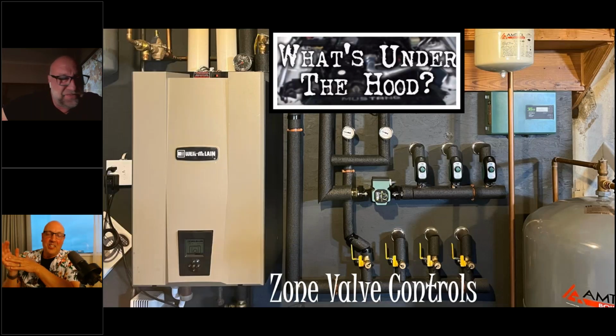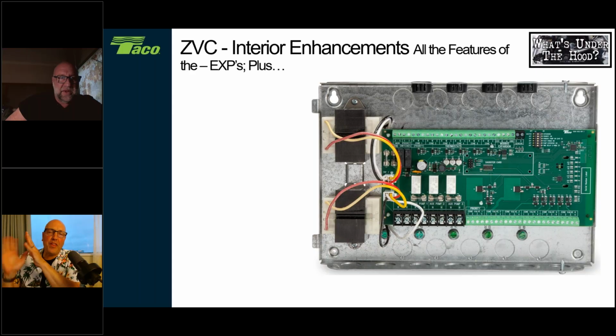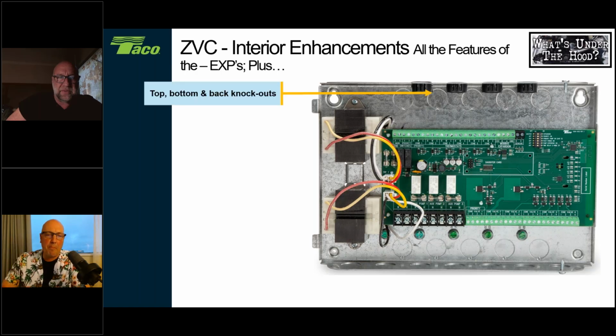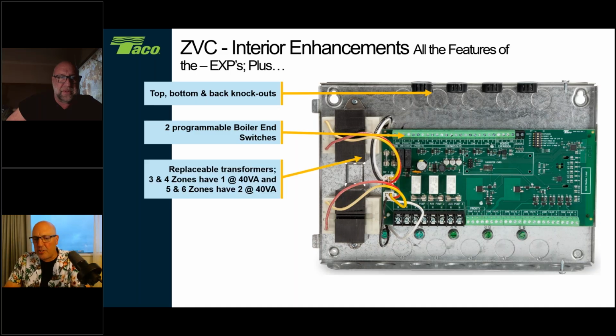All right. So let's jump back into this and talk about the zone valve controls. What did we do on the ZVC boards themselves? Everything that we had in the EXPs continues into the Dash 5s with a bunch of improvements. This board I love. There's a lot of neat stuff built into this. Again, the back knockouts that we had before, the programmable end switches that we saw before, the replaceable transformers. Now, when we look at the ZVCs, the 3 and 4 zone panels have 1 at 40 VA. The 5 and 6 have 2 at 40 VA. So you're probably not going to need to update that.